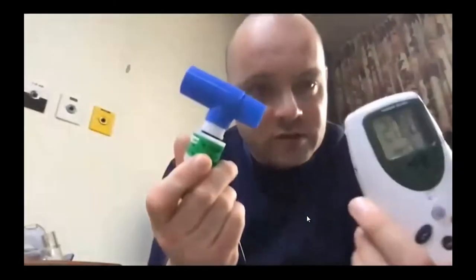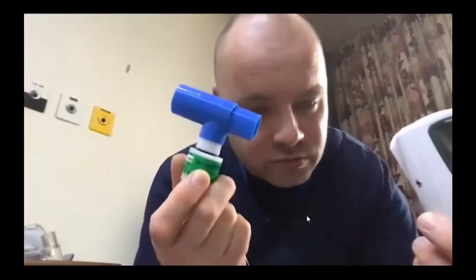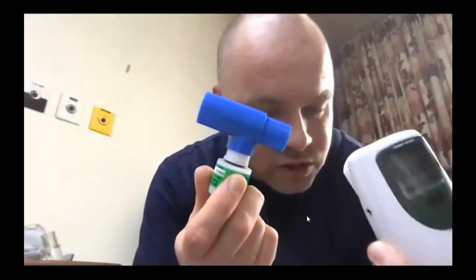As far as the FiO2, the way that spindle knob works, it's pretty precise. Obviously, if you're turning a knob through a quarter of a turn, and a quarter of a turn, and a quarter of a turn, it's not ideal, because you can't walk back to it and say, well, I'm still giving the same FiO2. Someone could have tweaked it a bit. So first prize is if you can have a portable O2 sensor that you can just T-piece in and walk around and check everyone's FiO2 that's been set. You can dial it back if it's too much, or you can increase it if you think it needs increasing.